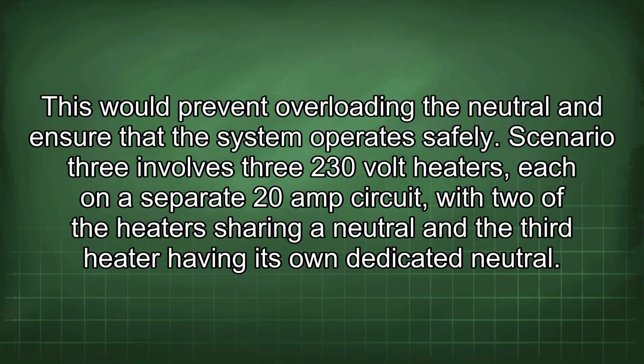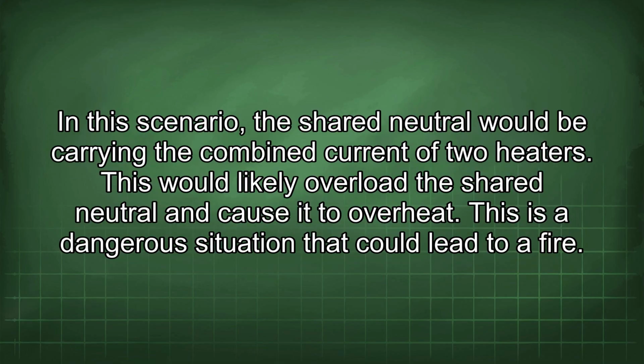Scenario 3 involves three 230-volt heaters, each on a separate 20-amp circuit, with two of the heaters sharing a neutral and the third heater having its own dedicated neutral. In this scenario, the shared neutral would be carrying the combined current of two heaters. This would likely overload the shared neutral and cause it to overheat. This is a dangerous situation that could lead to a fire.